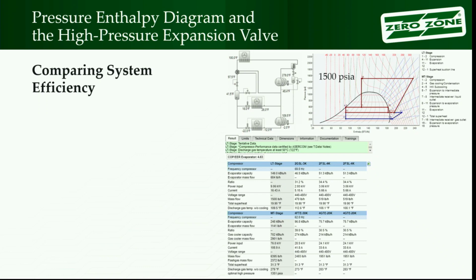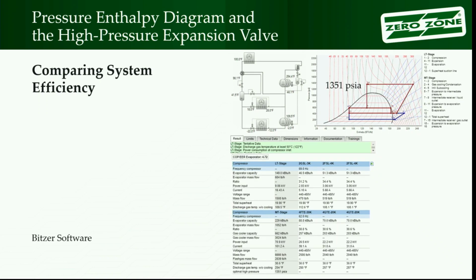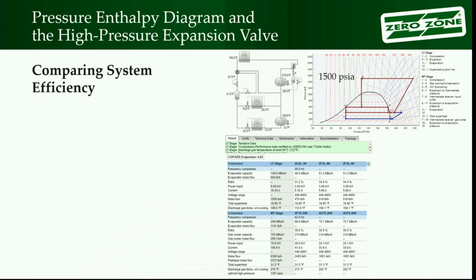Keep in mind, I'm still stuck, right? Still stuck on that 100-degree line because it didn't change. The temperature outside didn't change. Now do I have more or less flash gas? It's a little tricky. We'll go back. Get a little less flash gas. It's moved over subtly to the left. But I'll give you the tables here momentarily.